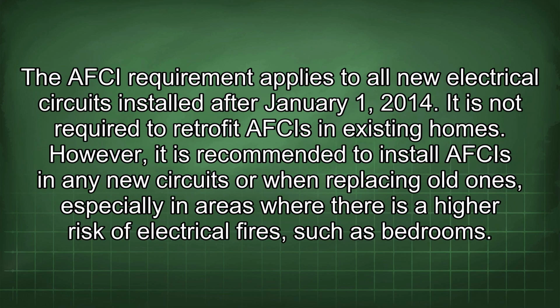The AFCI requirement applies to all new electrical circuits installed after January 1, 2014. It is not required to retrofit AFCIs in existing homes. However, it is recommended to install AFCIs in any new circuits or when replacing old ones, especially in areas where there is a higher risk of electrical fires, such as bedrooms.